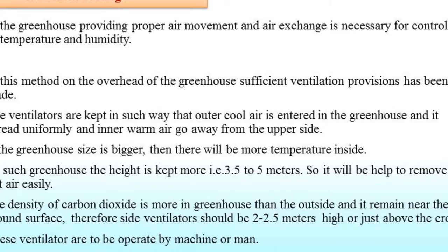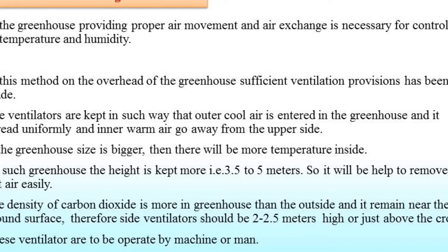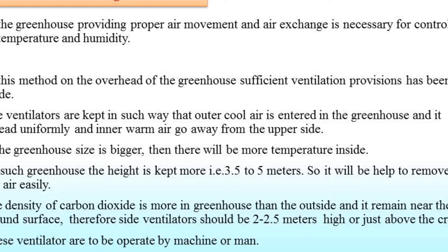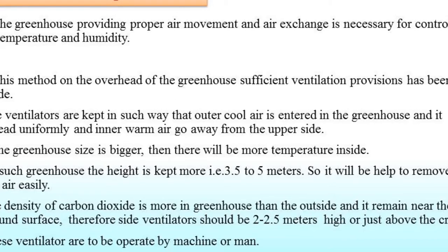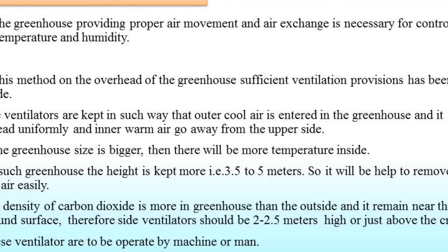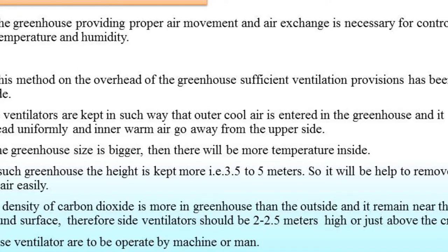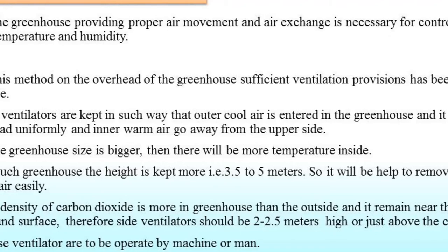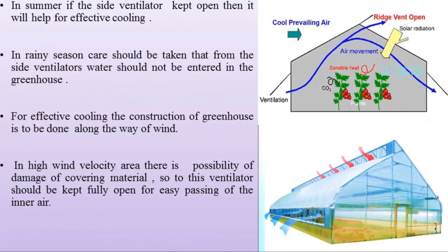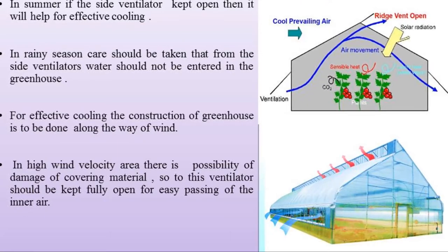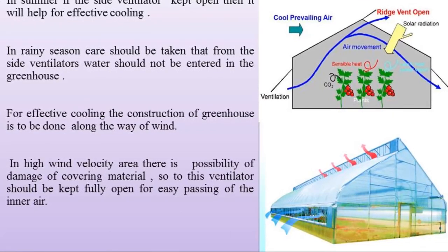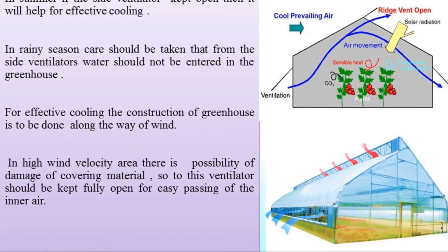The density of carbon dioxide is higher in greenhouses than outside, and due to its high density it remains near the ground surface. Therefore, the side ventilator should be 2 to 2.5 meters in height, or sometimes located just above the height of the crops. These ventilators are operated by machine or by man, and work efficiently in summer season. In summer season, the side ventilators are kept open, which helps to reduce temperature effectively.